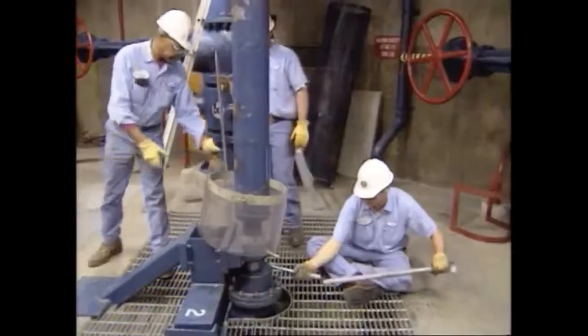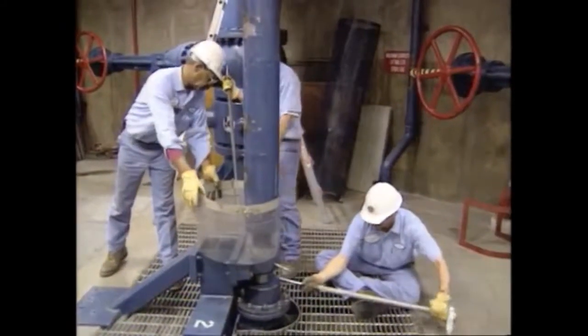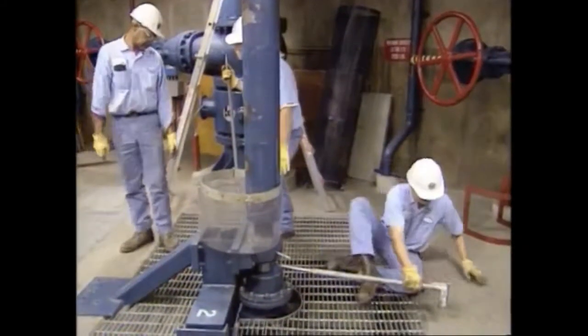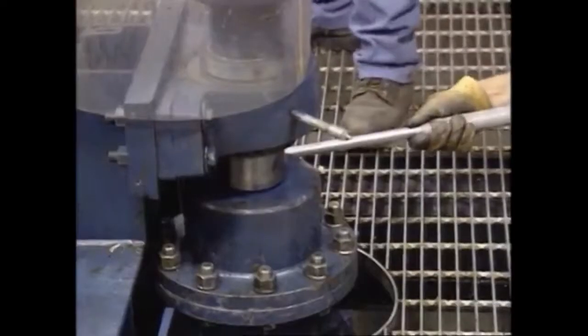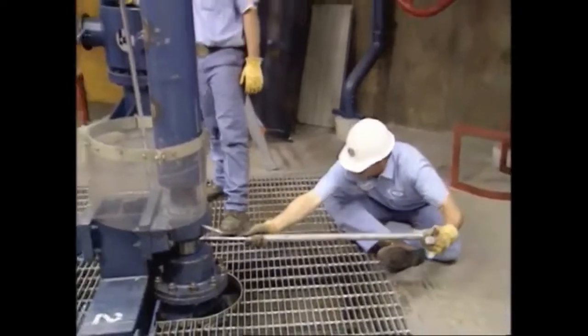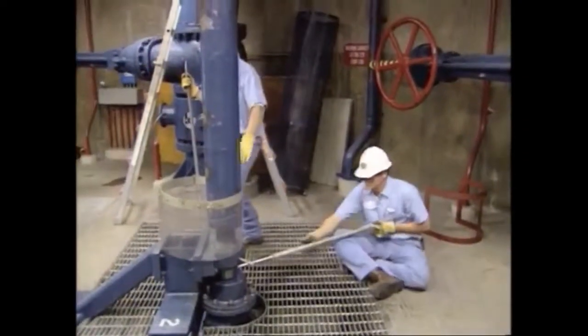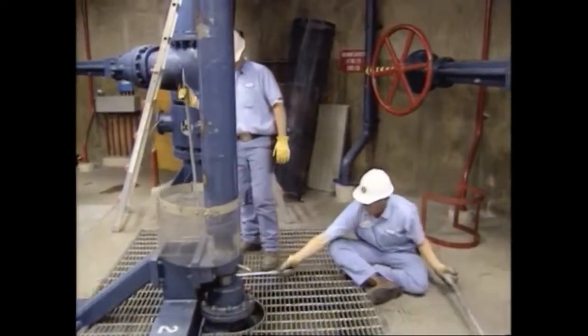When a pump is fitted with a mechanical seal, it must never be allowed to run dry, or the seal faces will be burned and ruined. Mechanical seals are not supposed to have any visible leakage from the gland. Of course, they may have slight leakage, which is vaporized. But if the leak is visible, the seal may require relapping, or it may have to be replaced.